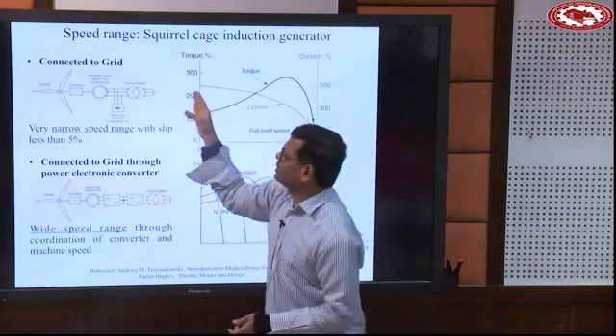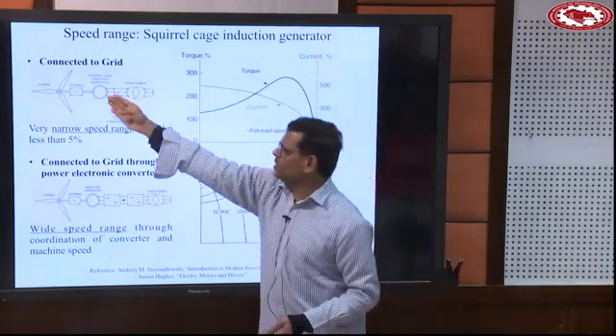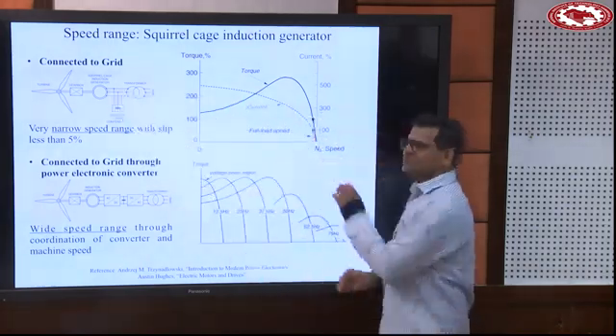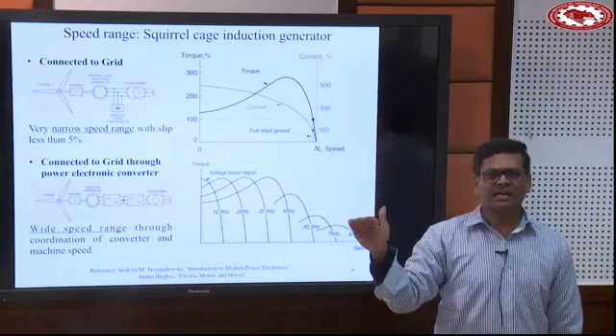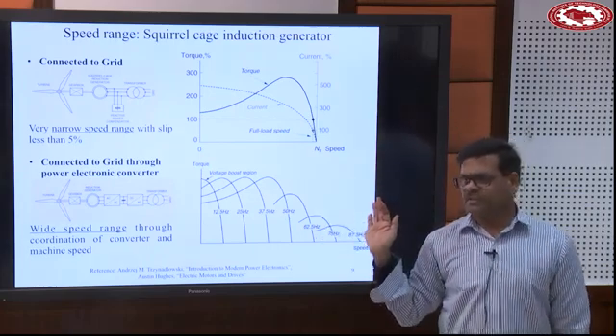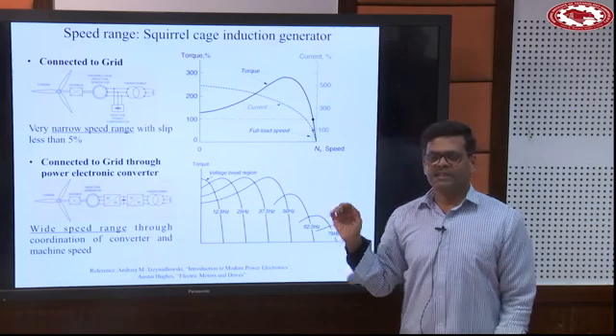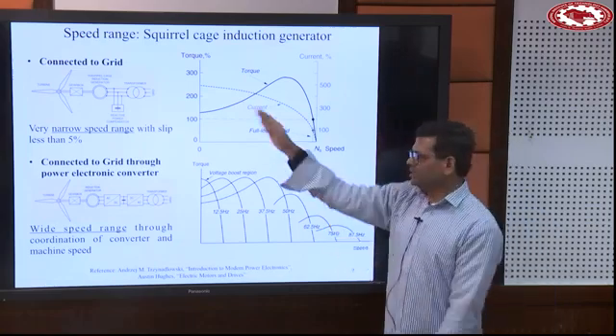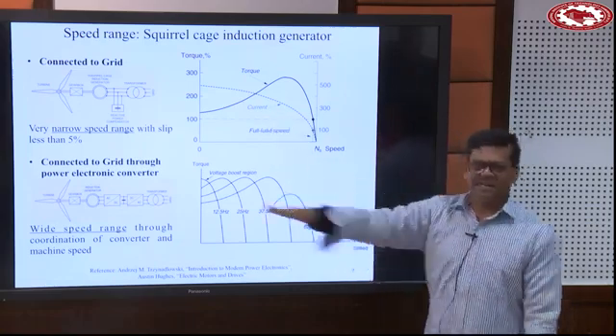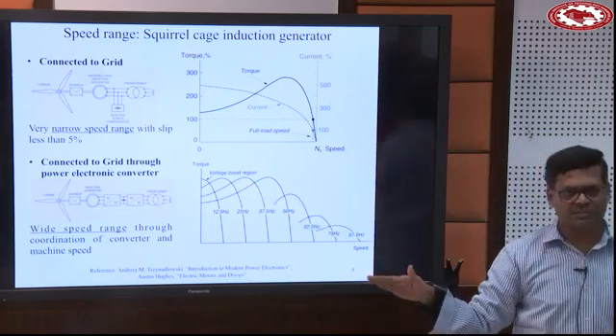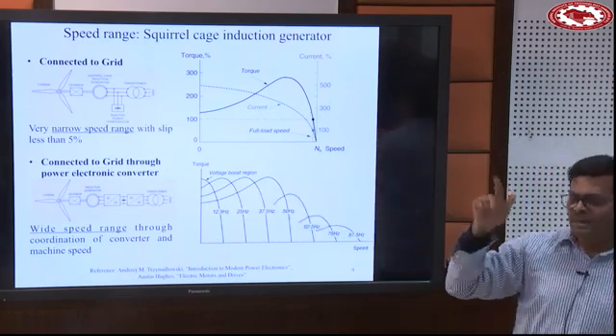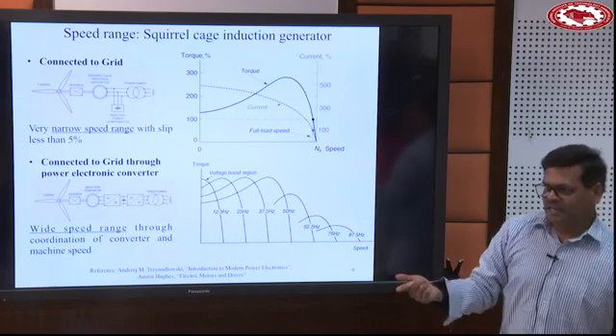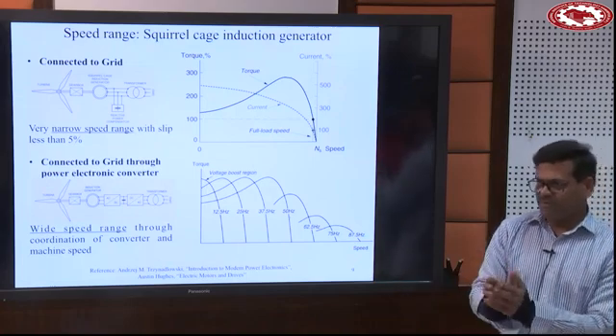If it is connected to the grid and if it is a 4-pole machine, then the magnetic field will always go at 1500 rpm. Is that understood? If it is a 4-pole machine connected to the grid, 50 Hz supply, the magnetic field will always go at 1500 rpm. The speed difference between the rotor and the magnetic field will be a very small number.